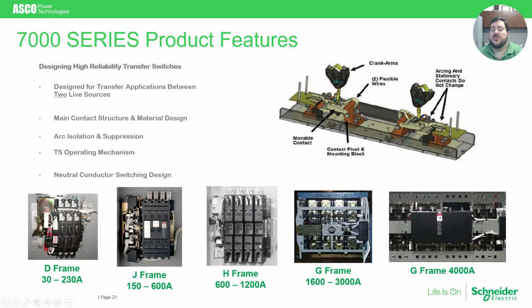Let's talk a little bit about the switch itself. So the ASCO platform has many different switch frames based on the ampacity of the equipment, really, ranging from the D frame, which goes from 30 to 230 amps, several ranges in between, all the way up to our largest, which is our 4,000 amp frame. All the frames are rated up to 600 volt applications, and the WCR ratings, the withstand ratings that we discussed earlier, vary based on the configuration and the breakers that are used. So please refer back to the rating tables on the website for those exact ratings.